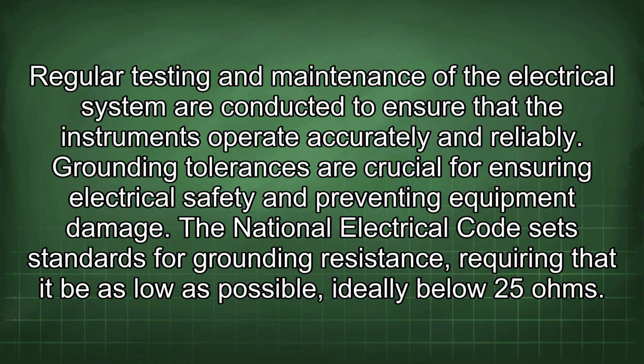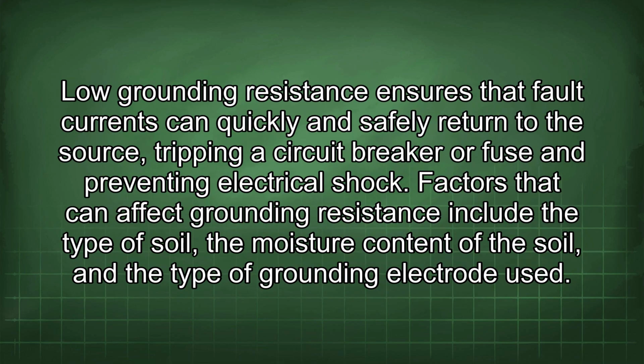Grounding tolerances are crucial for ensuring electrical safety and preventing equipment damage. The National Electrical Code sets standards for grounding resistance, requiring that it be as low as possible, ideally below 25 ohms. Low grounding resistance ensures that fault currents can quickly and safely return to the source, tripping a circuit breaker or fuse and preventing electrical shock.